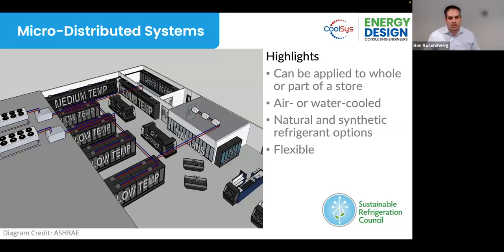So this here shows you a view of a potential retail store in 3 dimensions, where you can see that you can have multiple case lineups and coils for walk-ins that are in parallel and in series. And you can apply this micro distributed and self-contained architecture to the entire store, where you might have specialty merchandisers or island cases or custom cases. You can implement those with low GWP refrigerant options like propane and some others that we'll talk about, as well as connect the case lineups and coil units to, per se, a central water loop for energy efficiency purposes, up to some kind of dry cooler or fluid cooler on the roof. Again, you can leverage natural and synthetic refrigerant options throughout the store. This is highly flexible, and there's many different ways to look at it. Next slide, please.